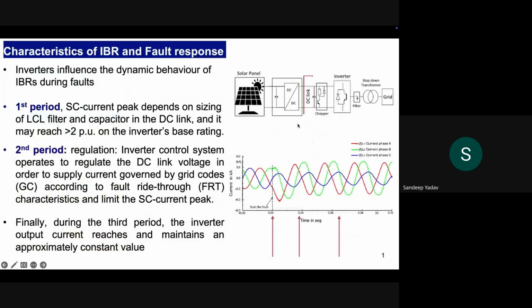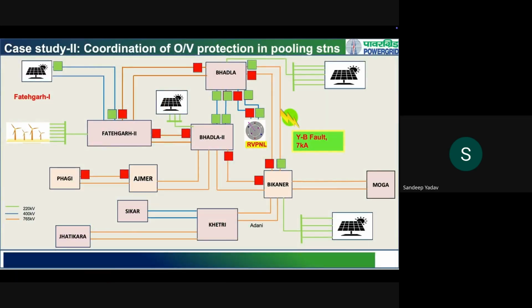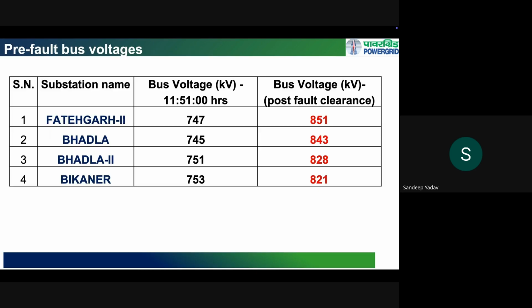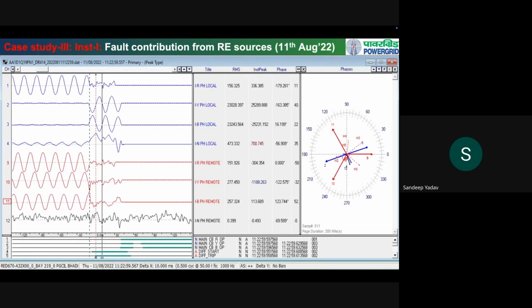So let's verify it from a real-time fault, or a real scenario in the system. The initial 4 currents are R, Y, B, and this is the neutral. These are from the grid side, and the bottom 3, R, Y, B, are the remote end, which is the solar plant end. If you take a look, this was a Y to B fault.